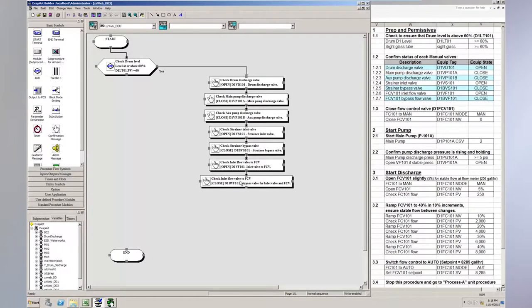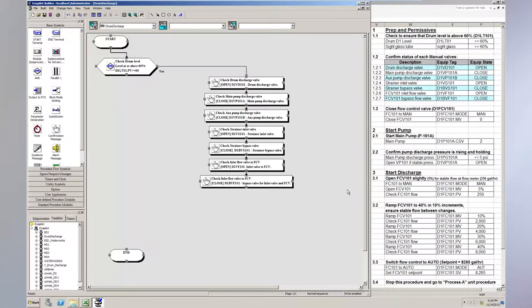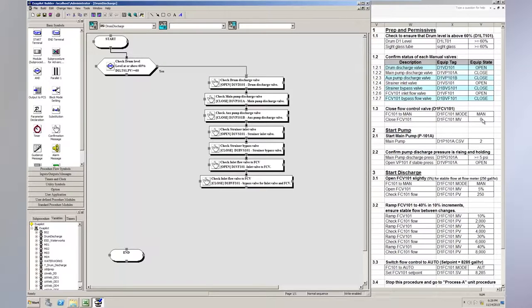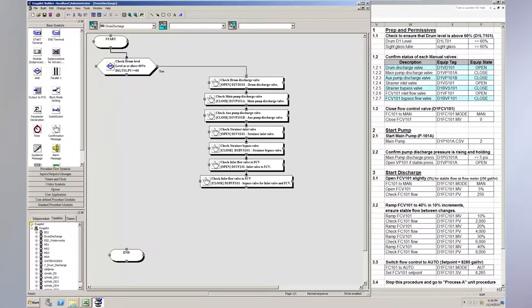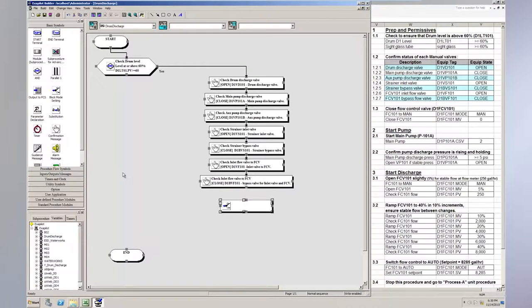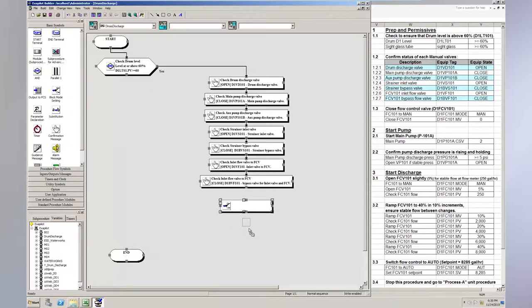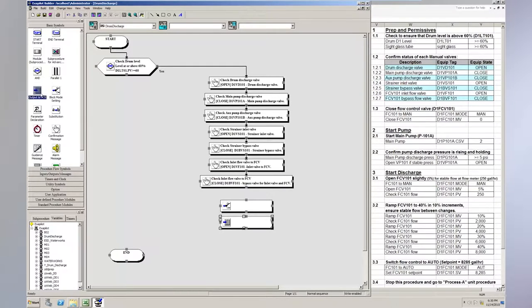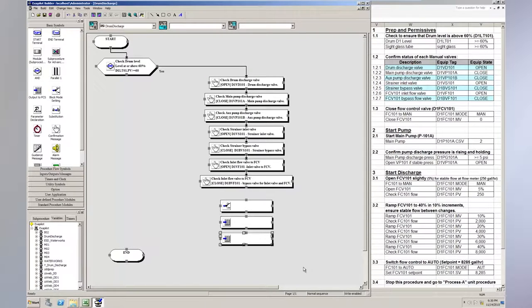And then I need to characterize it just to say yes. So if it passes this criteria, then I'll go on to this step of check drum discharge valve. And I'll keep flowing on down and so on until it gets to this last check. So once these things are all done by the operator, the next step is to put the flow control loop in manual mode and write a zero to the output to close that valve. Ensure that flow control valve is closed. And then we'll start up the pump. So what I'm going to do here is then grab a block mode setting object, drop that onto the screen, onto the project screen. And I'll drop down an output to PCS object onto the screen. This is to close the valve. And I need another output PCS to help me accomplish starting the pump.